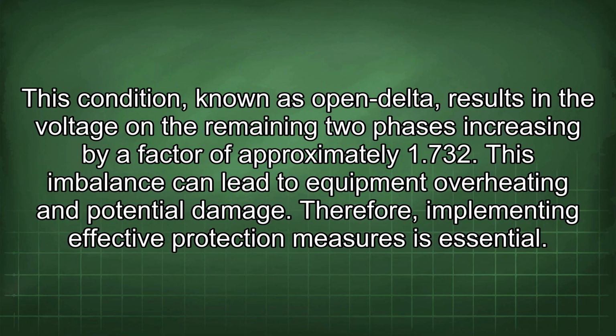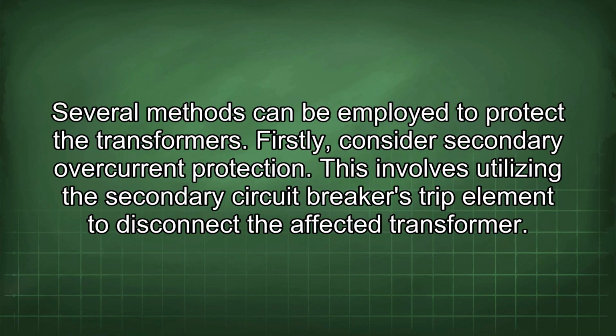This condition, known as open delta, results in the voltage on the remaining two phases increasing by a factor of approximately 1.732. This imbalance can lead to equipment overheating and potential damage. Therefore, implementing effective protection measures is essential. Several methods can be employed to protect the transformers. Firstly, consider secondary overcurrent protection.